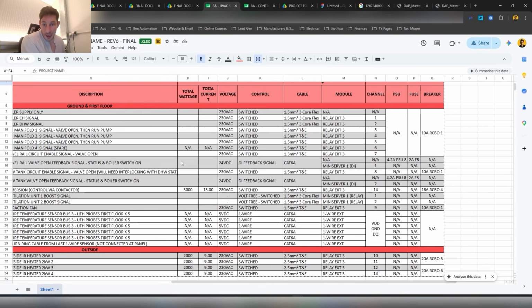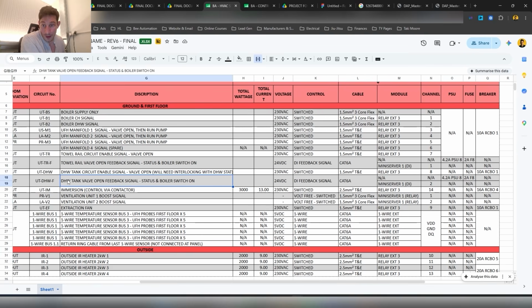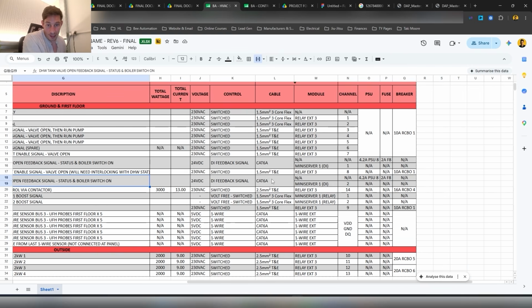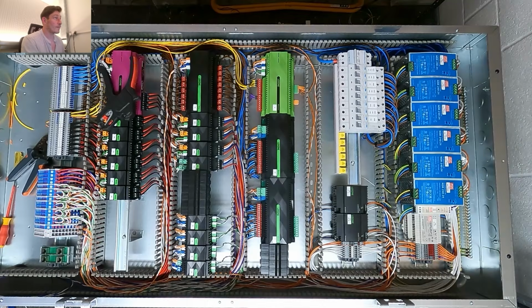Yep, so as you can see here on the schedule, these are the valve feedback signals. So when the valve is fully open, we can send back a signal to say yep, that's fully open, now we can switch on the pumps. You don't always have to do it this way, but this project required it to be done like this, basically. So you can see digital input 1, digital input 2. That's what I'm doing there.